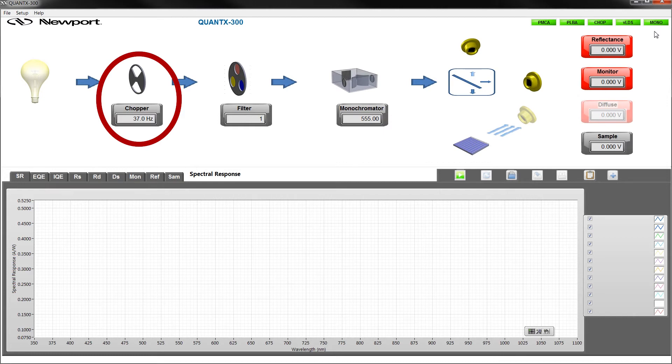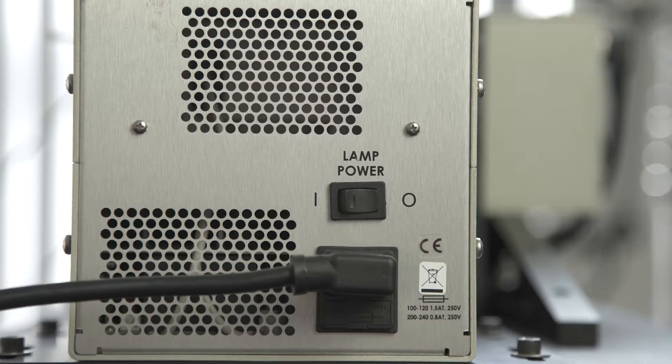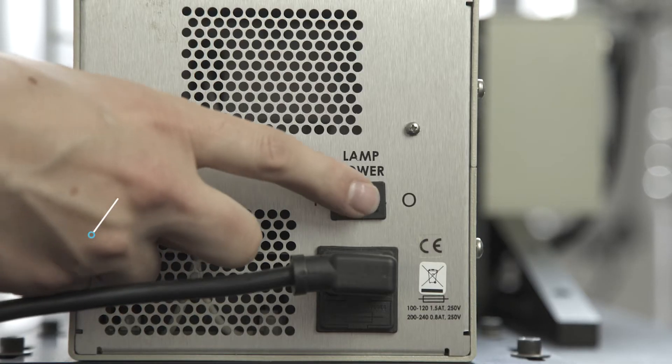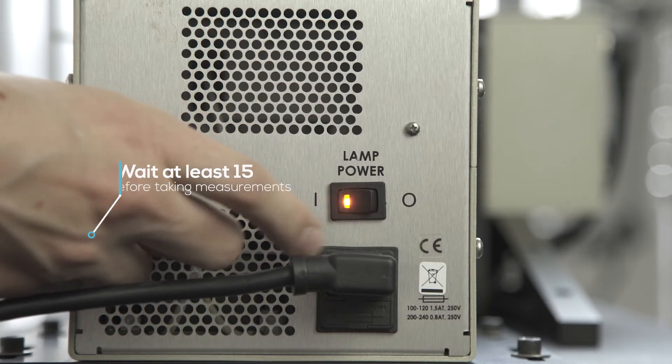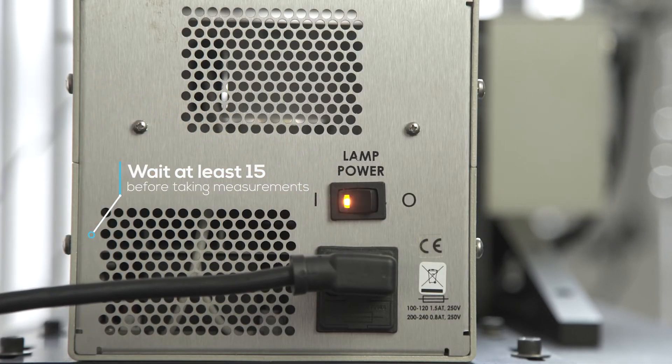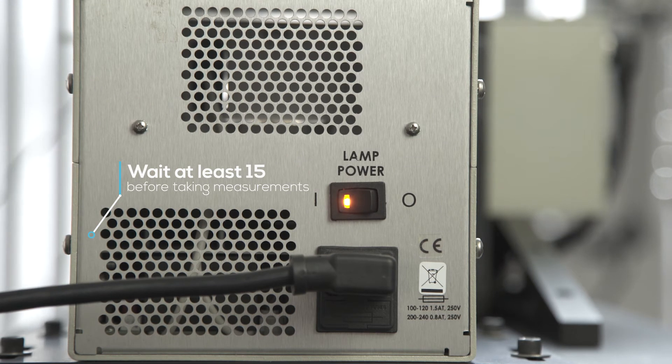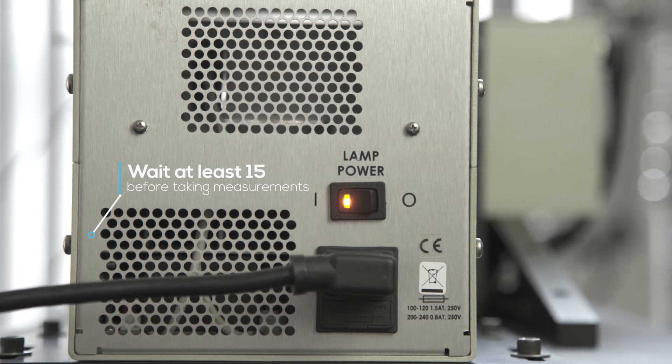Now we are ready to turn on the lamp, taking note that the chopper has been successfully enabled. It's recommended to wait at least 15 minutes for the light source to stabilize before taking measurements or calibrating the system.